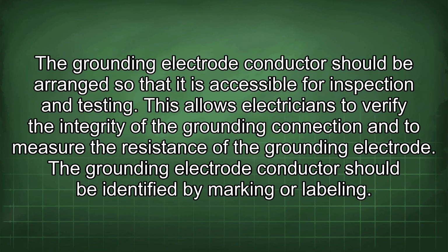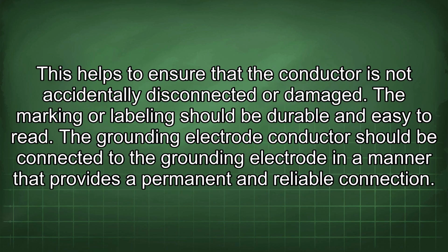The grounding electrode conductor should be arranged so that it is accessible for inspection and testing. This allows electricians to verify the integrity of the grounding connection and to measure the resistance of the grounding electrode. The grounding electrode conductor should be identified by marking or labeling. This helps to ensure that the conductor is not accidentally disconnected or damaged. The marking or labeling should be durable and easy to read.